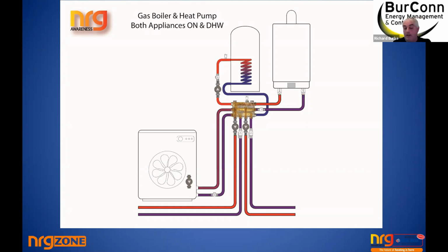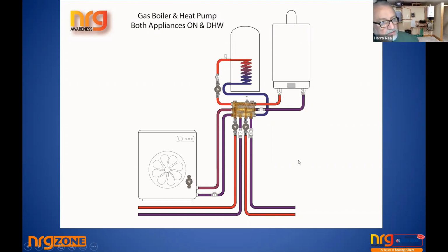And the one thing I did notice is the uptake on the condensing of the boiler. Now I know it's a very good boiler, but at one stage I think we got about 800 milliliters within about half an hour of the boiler working.